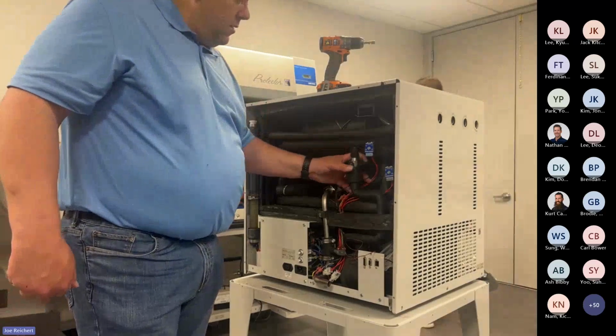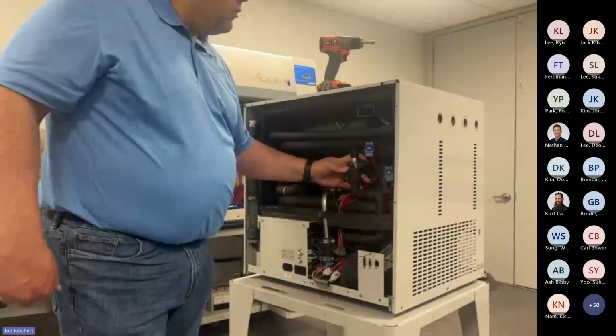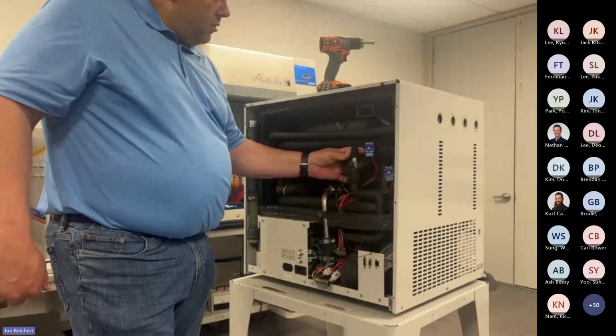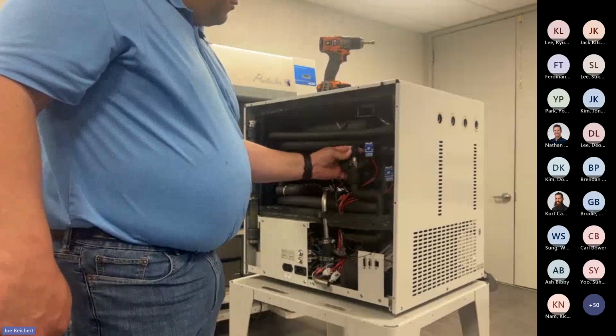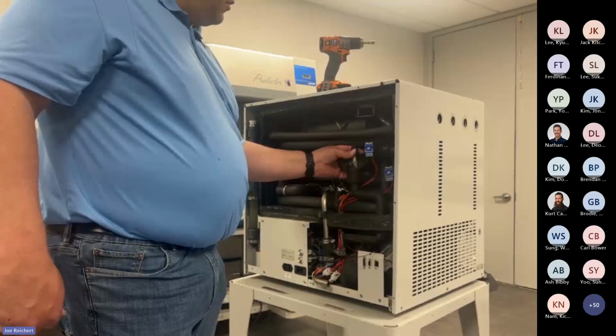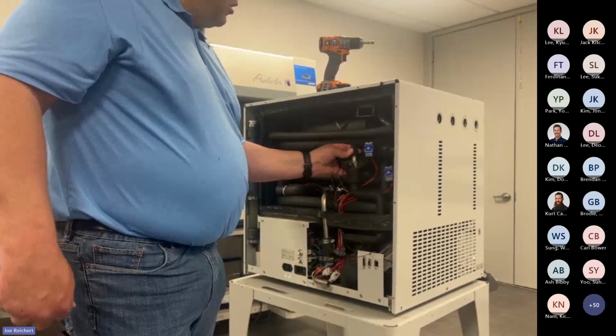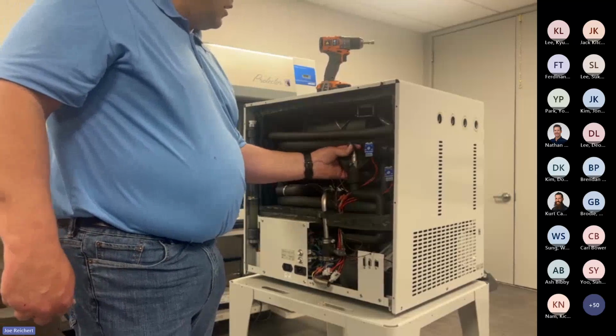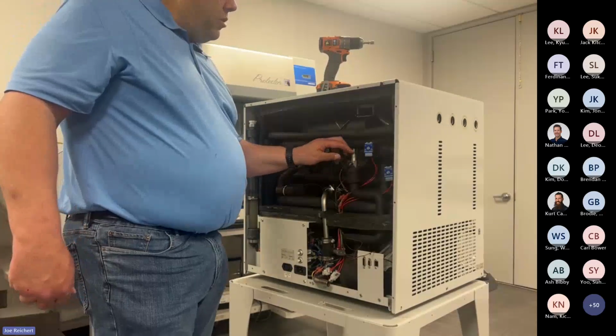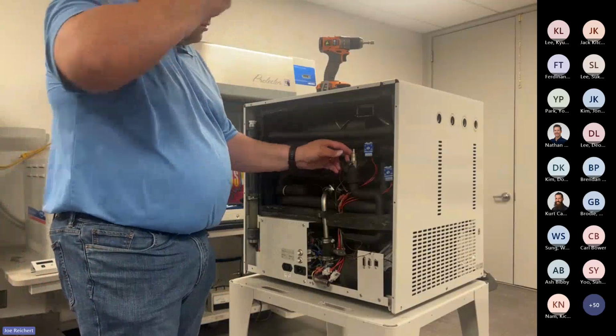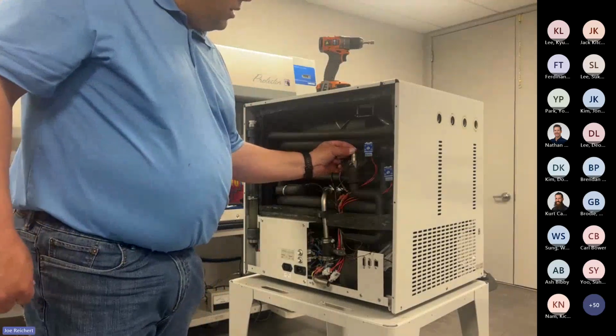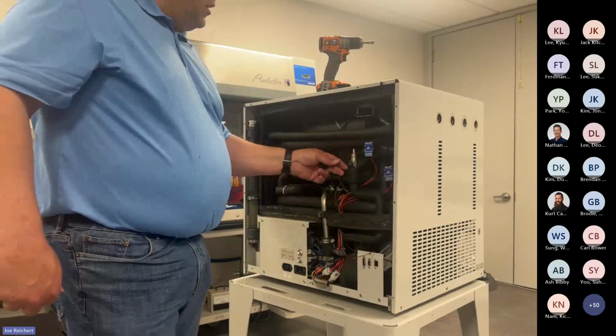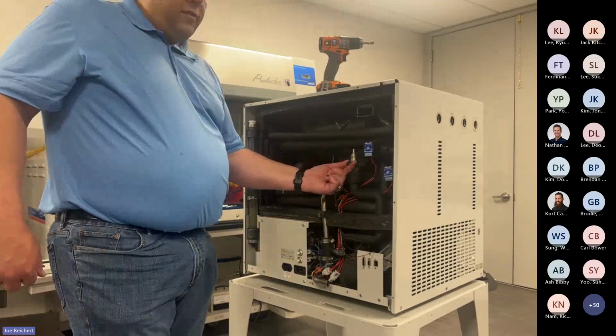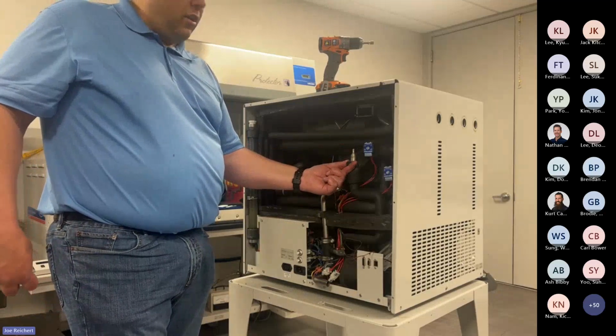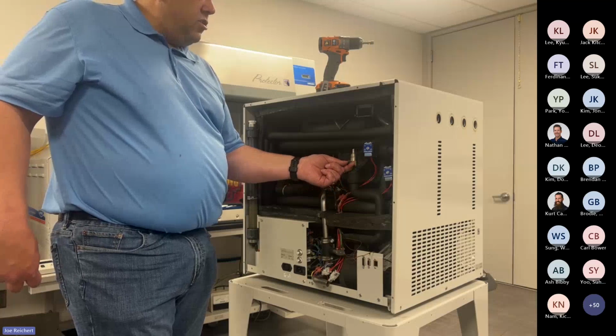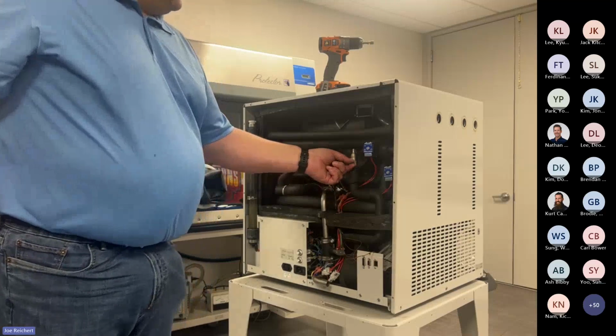There is a king valve right here on the unit. It has a little black cap on it. You just take that off, and there's a little square fitting on top of it. There is a special tool to open and close that with a square type wrench. I have used pliers before in the past. That's just something you don't want to do too often, because you can really scar up the top of this valve. This fitting comes off. This is a 3/8 flare nut fitting, exact same fitting as you have on refrigeration lines.